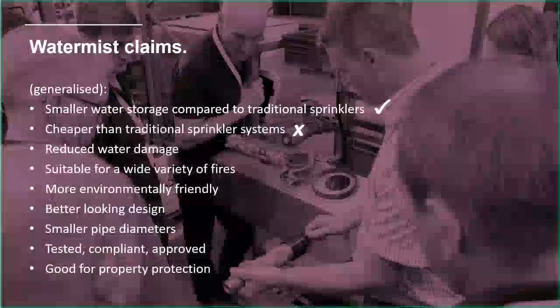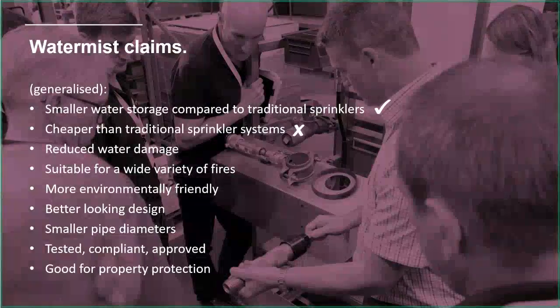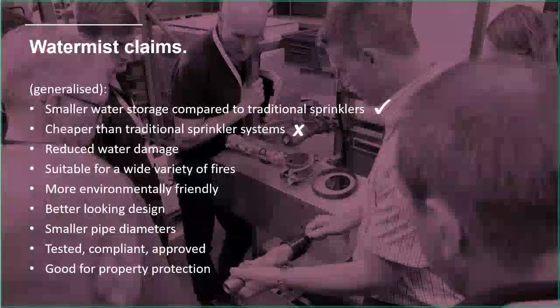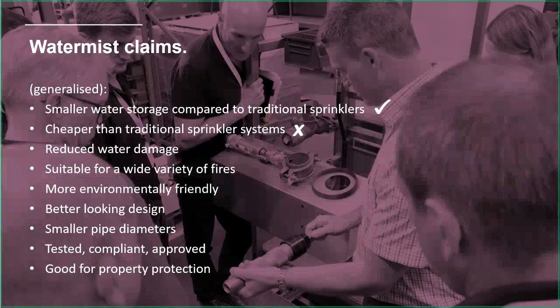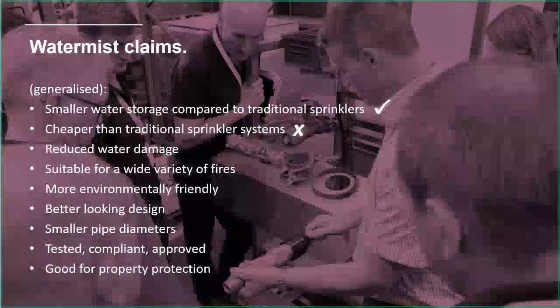With mist systems, the prices vary a lot depending on which manufacturer you go with and what operating pressures you're looking at. So it is possible that mist would be cheaper than sprinklers, but if it is, it won't be by much, and often the mist system is actually more expensive. So the generalization that water mist is cheaper than sprinklers, I'd say is false.